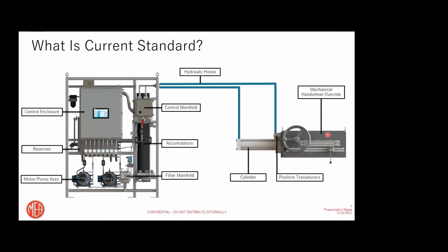valves. Basically, at this point in time, you have some type of hydraulic power control unit, which is connected to the actual actuator. So usually you have a setup where you have a mechanical override connected to the valve, and you have a hydraulic cylinder, which is also connected to the stem of the valve and to position transducers. Then this cylinder is connected with hoses to the hydraulic power control unit, which basically looks something like this.